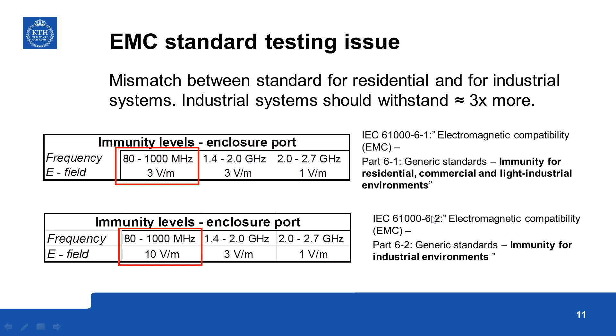For normal residential and offices, it is 3 volts per meter. So up to 3 volts per meter, it should withstand. Even if it fails at 4 volts per meter, it doesn't matter. Still, it is as per conformity. Whereas if that equipment is to be used in an industrial environment, the specification is 10 volts per meter because you have a harsher environment in the industry for this particular frequency. For other frequencies, they tend to be the same. So the environment where the equipment is to be used, that also is coming into these standards.